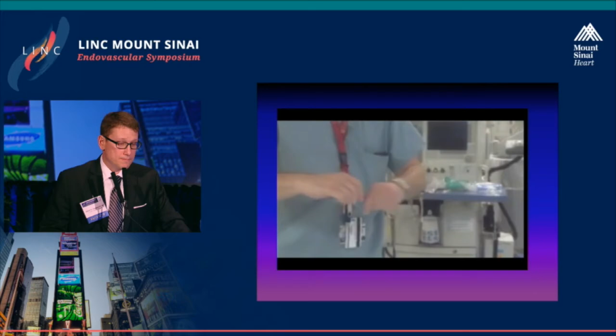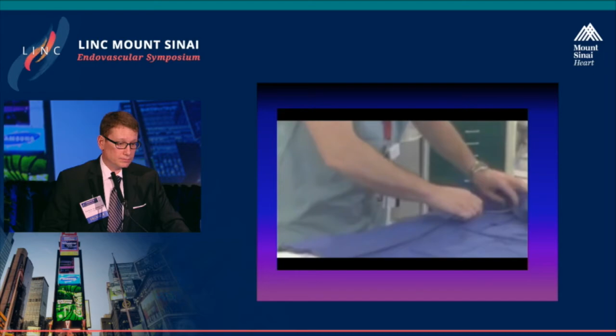So now we've gotten the exchange system, taken the extension cable, and screwed it onto the back of the existing cable so we could exchange out our faulty sheath. We've gotten the larger internal diameter dilator inside the 12 French recovery sheath, which then just easily goes over, and now we should be able to retract the device that previously would not come back into the standard delivery sheath.